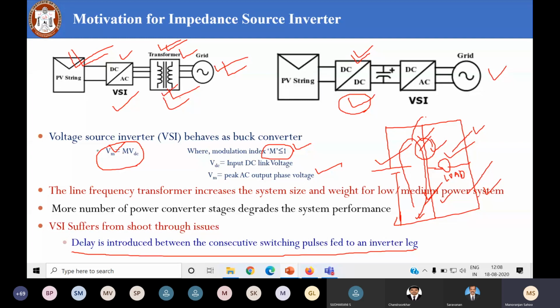So this inherently introduces a delay to your desired output voltage. At the time you want a certain output voltage, the delay causes an error. Because of that error, there may be more THD, total harmonic distortion, since the moment you want to turn on plus VDC, it doesn't happen right away because you need the delay to protect the circuit. So your output voltage gets delayed and distorted, resulting in more THD, more harmonics.